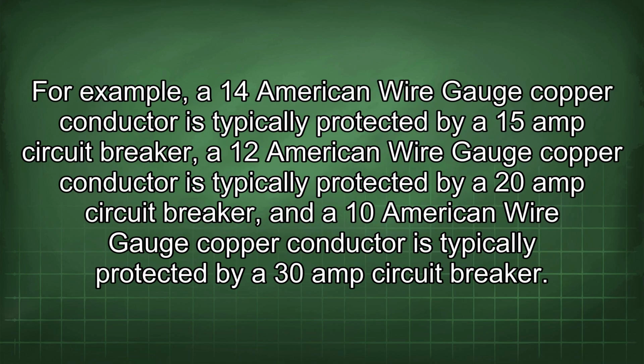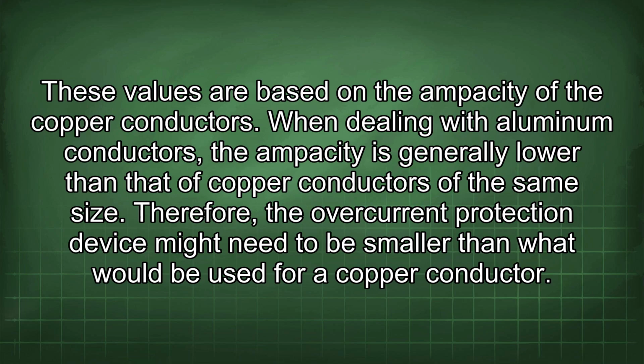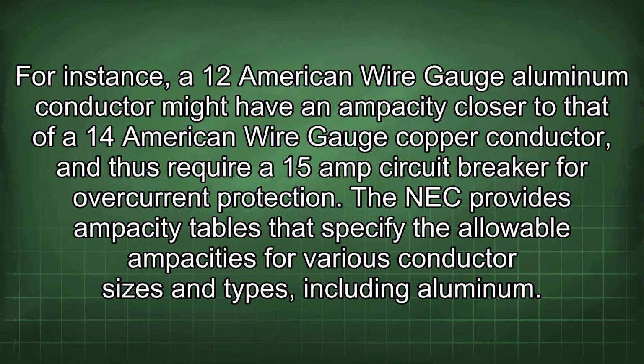For example, a 14 American wire gauge copper conductor is typically protected by a 15 amp circuit breaker. A 12 American wire gauge copper conductor is typically protected by a 20 amp circuit breaker, and a 10 American wire gauge copper conductor is typically protected by a 30 amp circuit breaker. These values are based on the ampacity of the copper conductors. When dealing with aluminum conductors, the ampacity is generally lower than that of copper conductors of the same size. Therefore, the overcurrent protection device might need to be smaller than what would be used for a copper conductor. For instance, a 12 American wire gauge aluminum conductor might have an ampacity closer to that of a 14 American wire gauge copper conductor, and thus require a 15 amp circuit breaker for overcurrent protection.